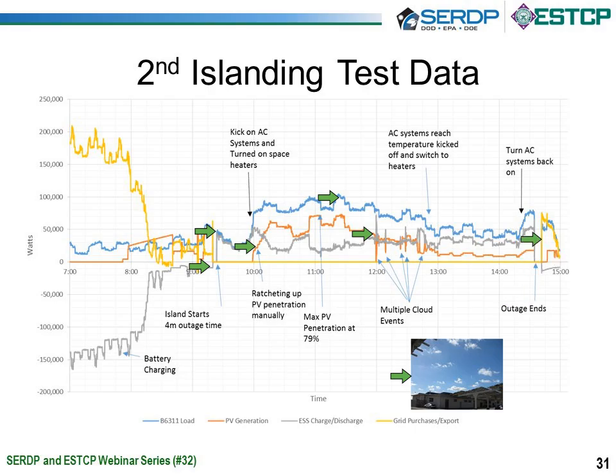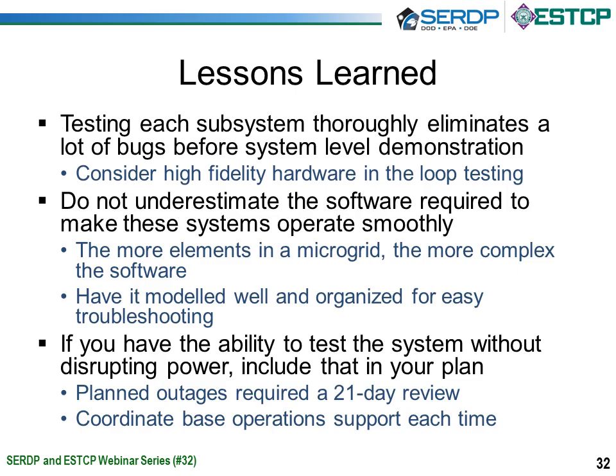So at this particular point, the system shut down. We ended the outage roughly about 3 o'clock, a little bit about 2-something in the afternoon. Reconnected the system roughly about 2:45, allowed power to get restored to the building, and let the PV system kick back on. Pretty exciting time in terms of end-to-end getting through a full islanding event and the results that came upon it. Did a lot of post-data processing to make sure that power quality was maintained, and so far, everything was managed per the IEEE guidelines.